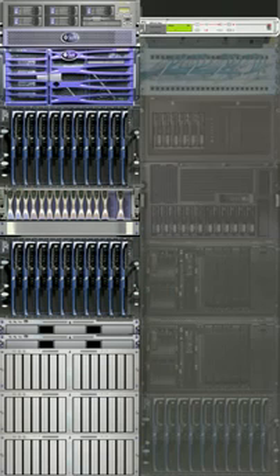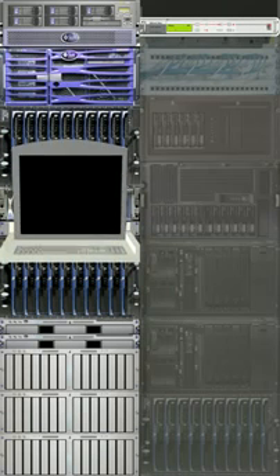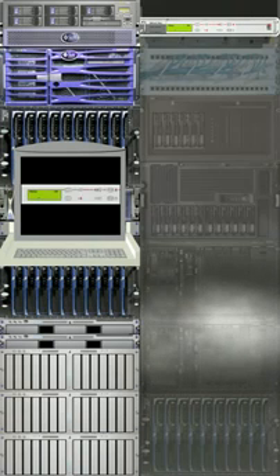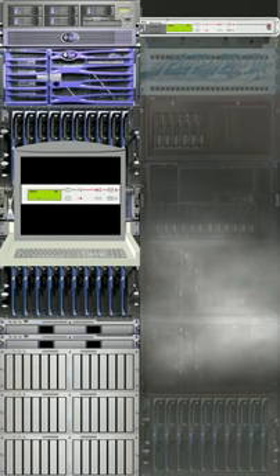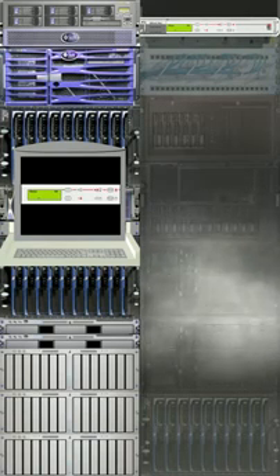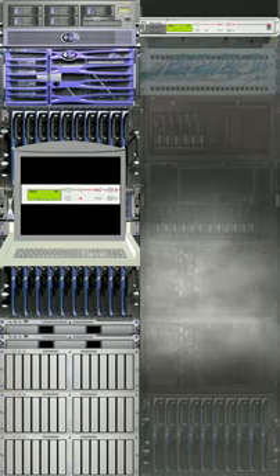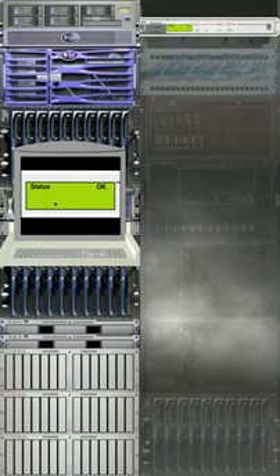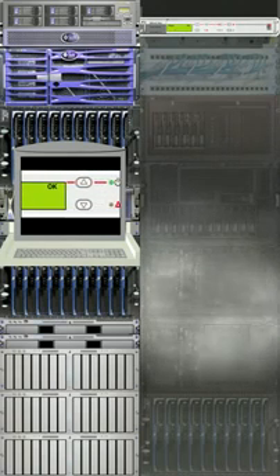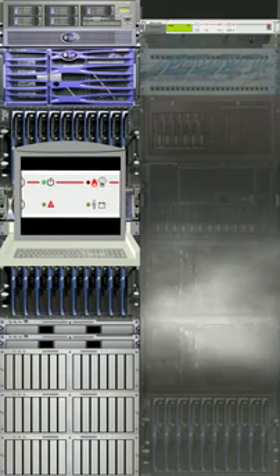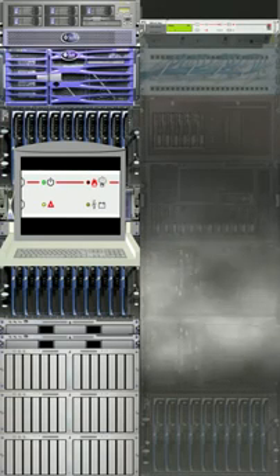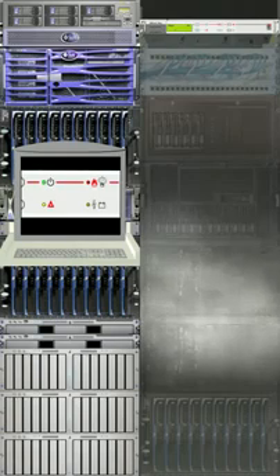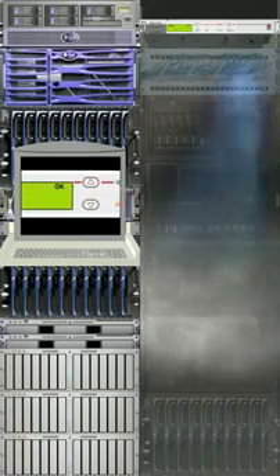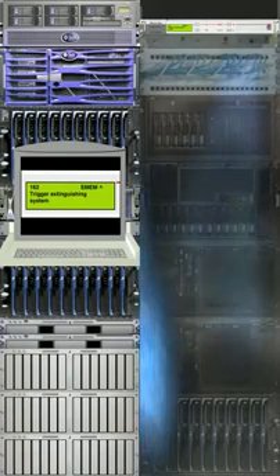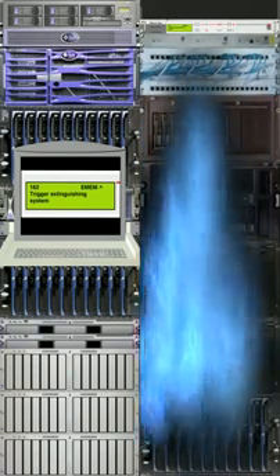The DET-AC Plus from Rittal is a 1U fire protection system that mounts into a standard Rittal IP55 enclosure. The DET-AC Plus detects smoke by drawing in the exhaust air of the active equipment within the rack. Utilizing 2 highly sensitive optical sensors, they can detect minute particles of smoke even in the early stages of a fire, the pyrolysis phase. If the first smoke alarm detects smoke particles, a pre-alarm is triggered. If the second alarm likewise detects smoke, then the extinguisher system is activated and the Novec 1230 gas is released into the rack, therefore preventing a risk of a major fire from developing.